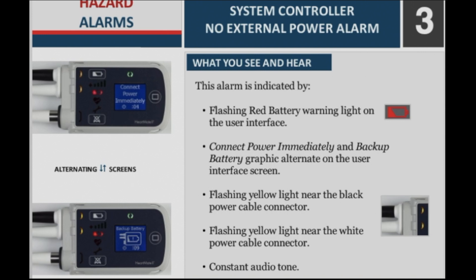System controller no external power alarm — what you see and hear. This alarm is indicated by: a flashing red battery warning light on the user interface; connect power immediately and backup battery graphic alternate on the user interface screen; a flashing yellow light near the black power cable connector; a flashing yellow light near the white power cable connector; and a constant audio tone.